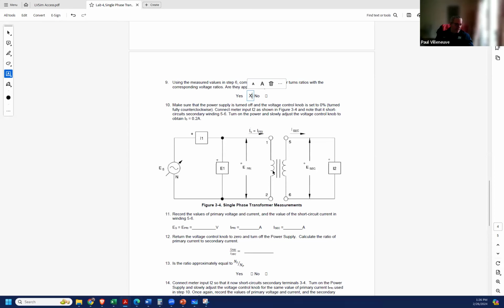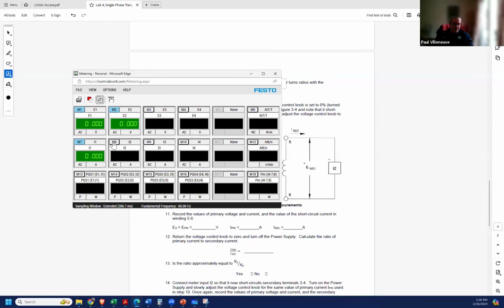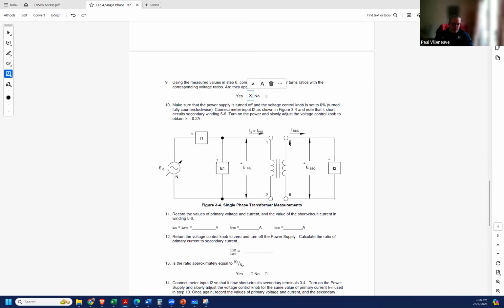So I've got to go back up and set my metering up, turn this one on, turn this one off. This is the source voltage. This is the primary current. This is the secondary current. Now, I've got to be very careful, because I'm putting a short circuit on the secondary of the transformer. That's the concept when we talked about full load or load loss tests or short circuit tests. We've got a lot of current potentially flowing in the secondary.